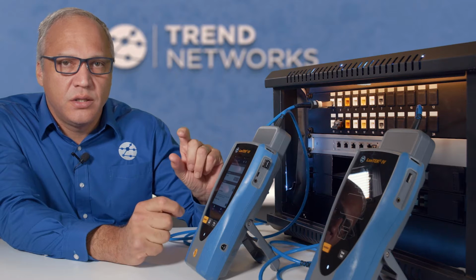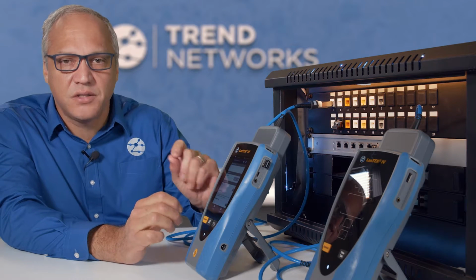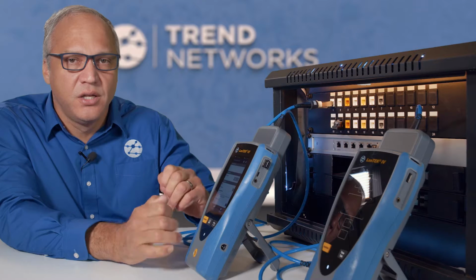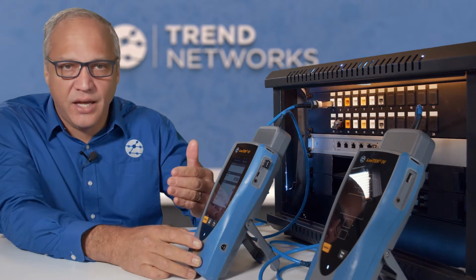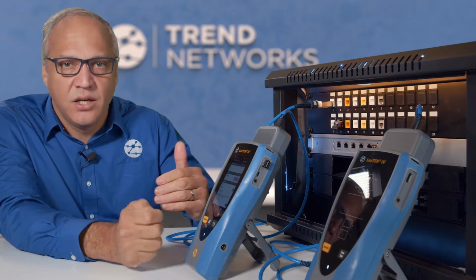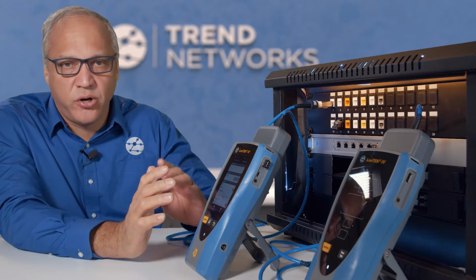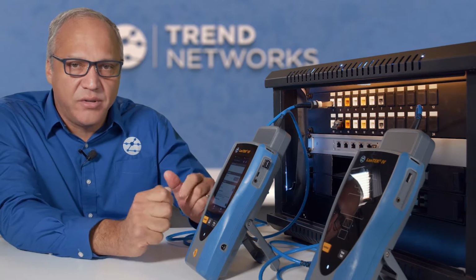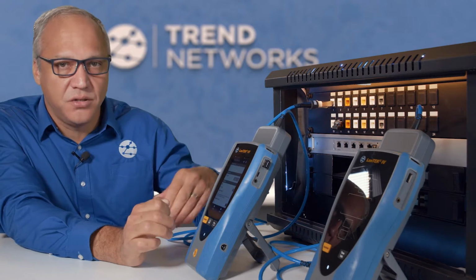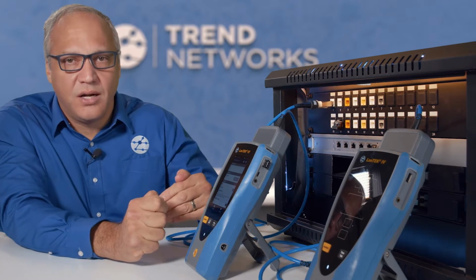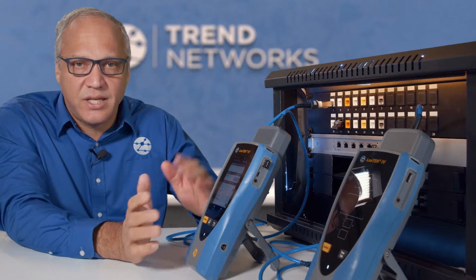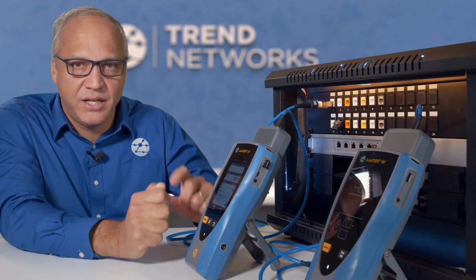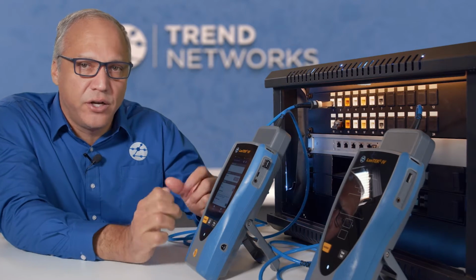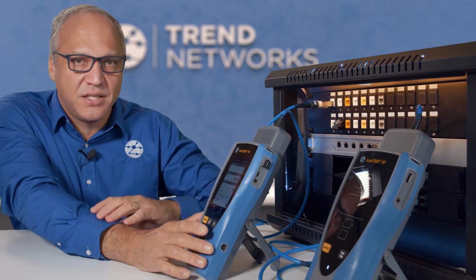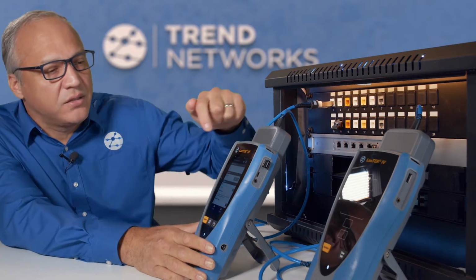So the Autotest defaults is a setting that will configure the default test type whenever you create a new job. If you're always doing a Cat 6a test or Class E, whatever the type, and that's the vast majority of the work you're doing, then when you create a new job, instead of having to go in and set it to that category, using this setting it will set that job to that test standard by default. That just saves steps when configuring a new job when you are usually testing the same type of cabling. So let's look at how to do that.